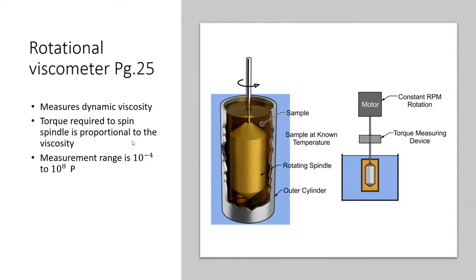The rotational viscometer has a motor, involves rotation, and therefore involves force — so we know we're measuring dynamic viscosity. The principle: it measures the torque required to spin an object in the sample. The amount of force required is proportional to the viscosity. If the fluid were water, the drum would spin relatively easily; if filled with honey, you'd need to constantly apply force. That force is proportional to the viscosity.